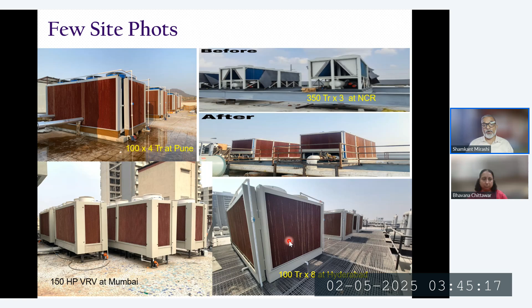It consumes less water compared to a cooling tower, because in a cooling tower there isn't just evaporation, there are also pilferages and so on, so all that is avoided. Water is handled within a very small space, so not too much maintenance is required, no chemical dosing, nothing. Very low maintenance.